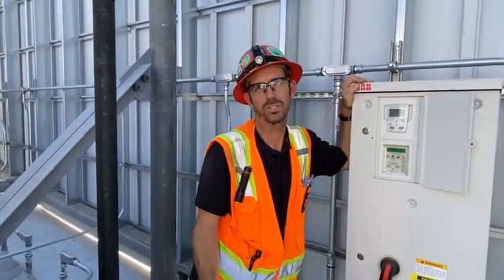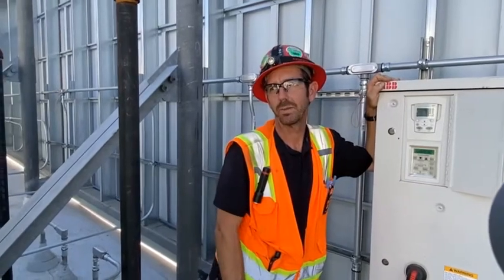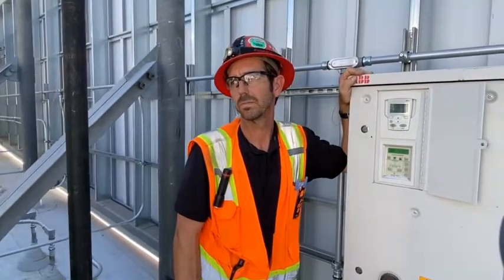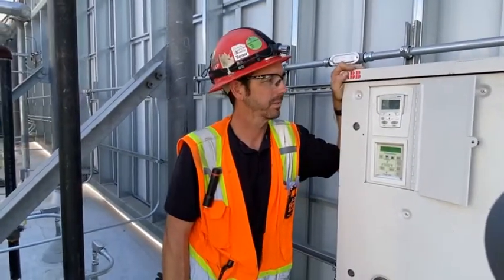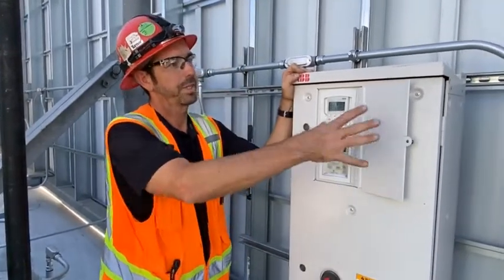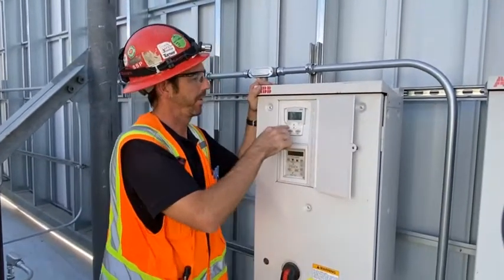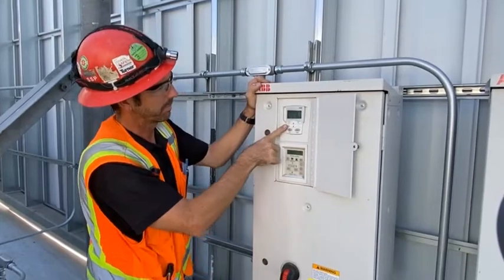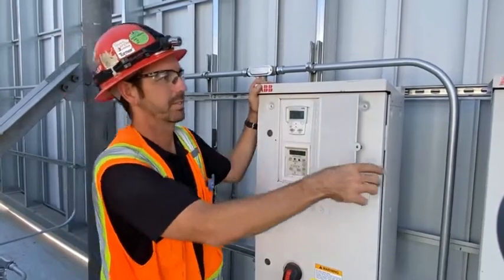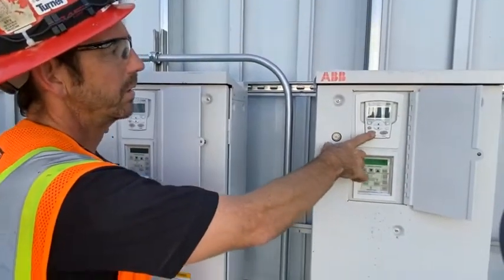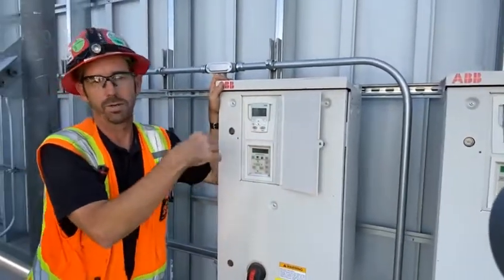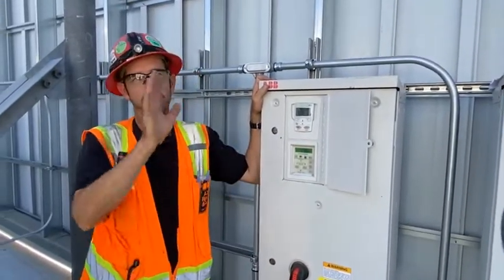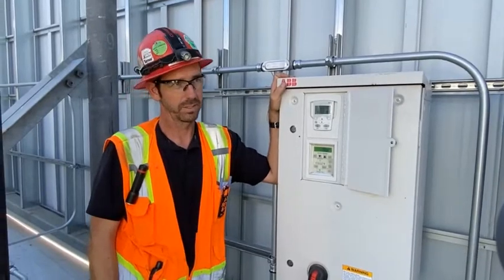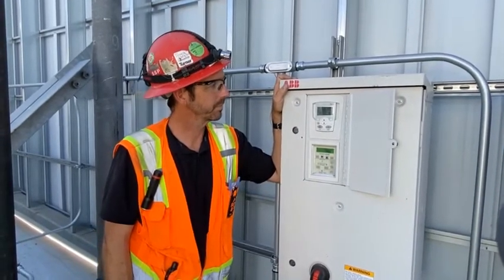Are you guys controls too, or would that be Kevin? Well, we talked to Kevin. Okay, perfect. The most important thing about these again are auto and the keypad. It's not going to do anything right now. They're not sending it a speed reference. But until Doug is done integrating, I don't want to leave it in auto in case this thing goes to a setting we don't want it to right now.